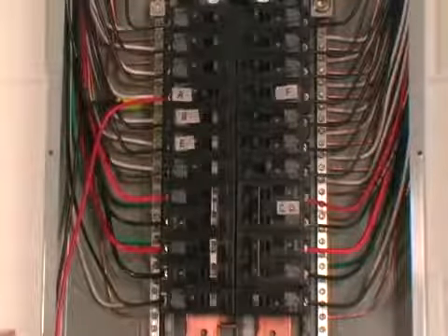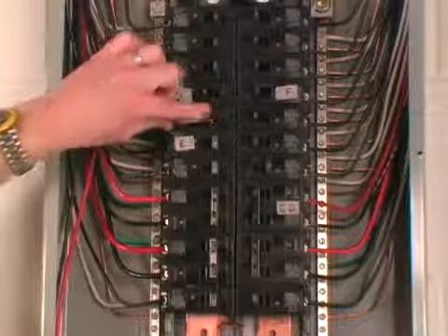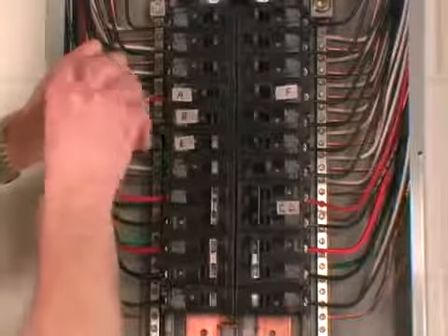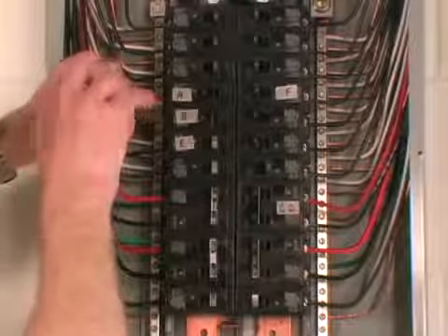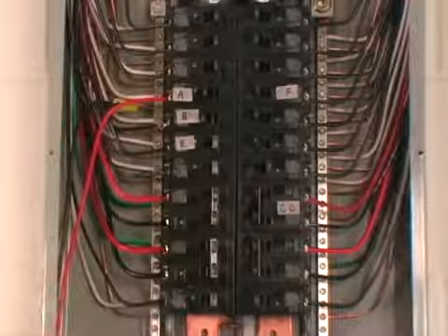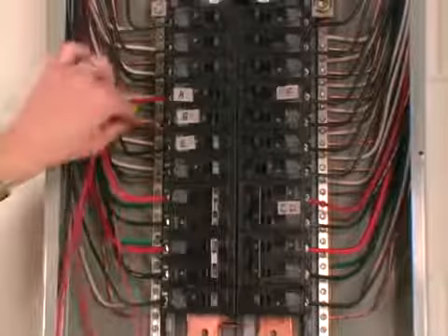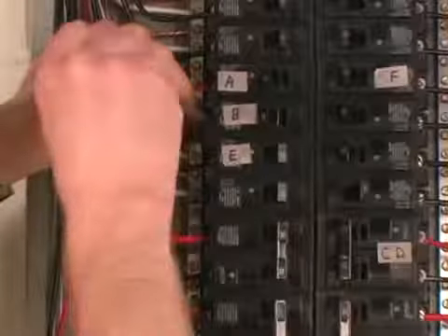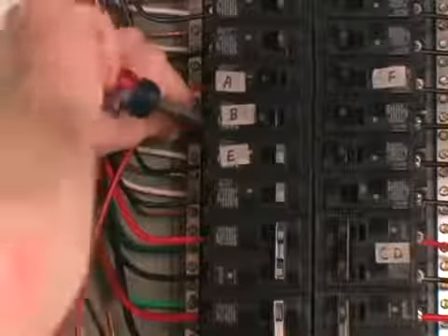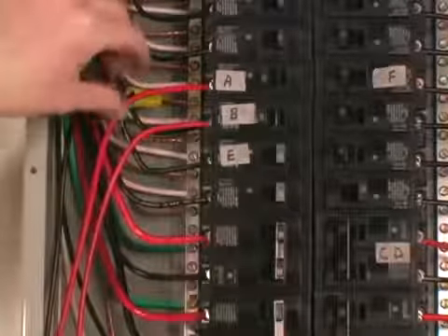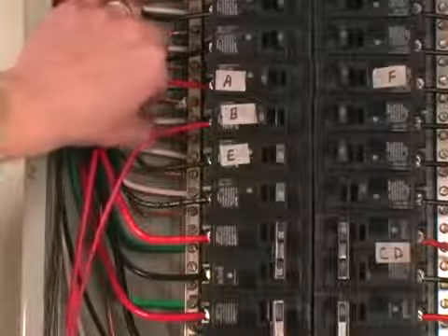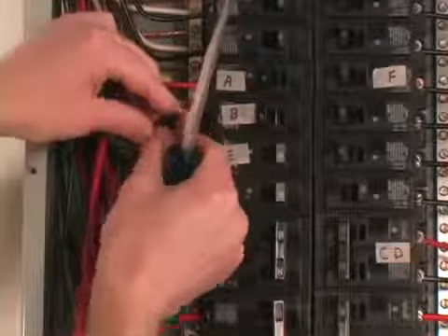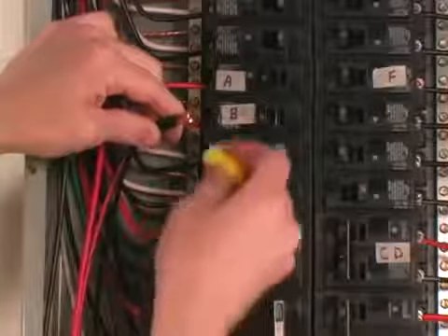Repeating that procedure for the B circuit, we'll turn off the breaker, remove the wire, take the red wire labeled B from the transfer switch, put it in the breaker, take the black wire labeled B from the transfer switch, and attach it to the wire that we removed from the breaker with a wire nut.